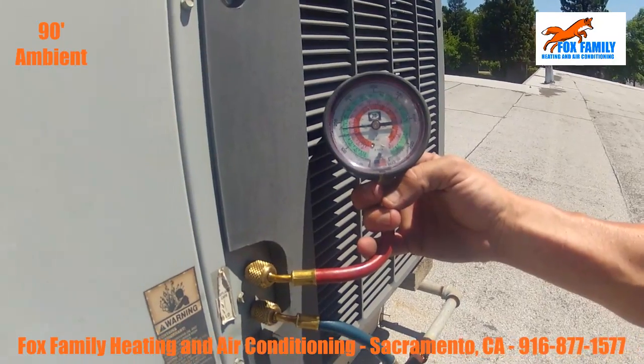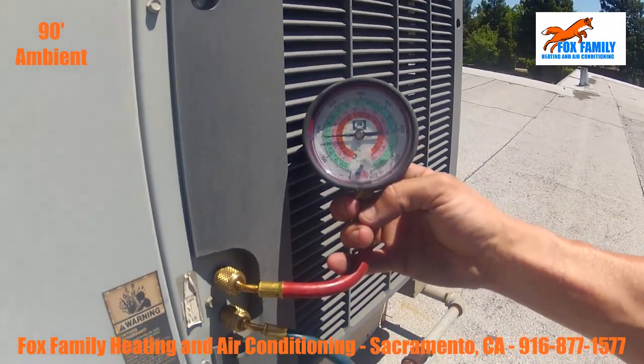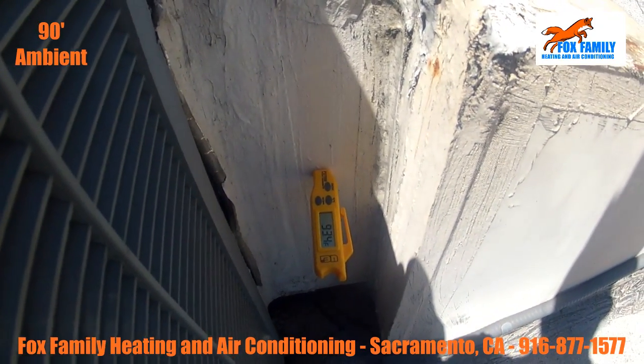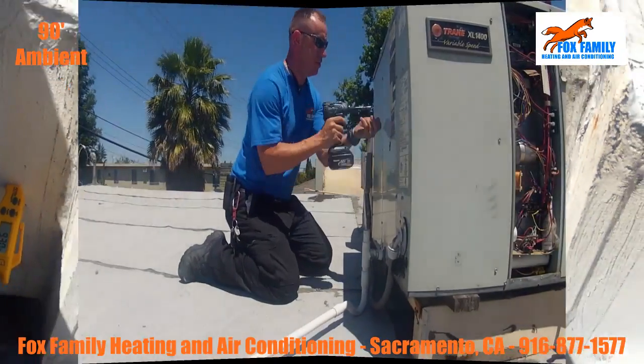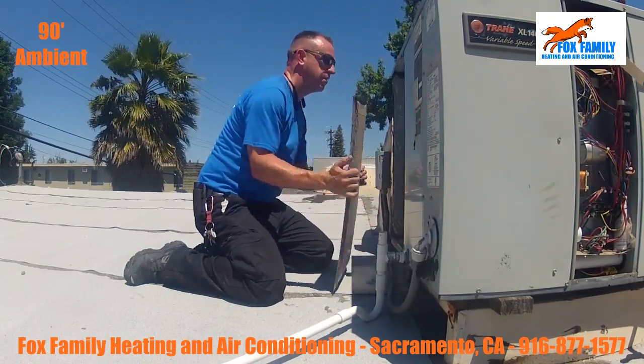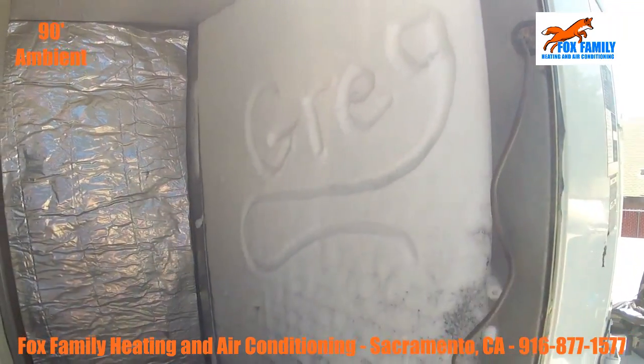And here we're at about 90 degrees saturation. And on a 90-degree day, that's not very good. Still at 93, that's not very good. Hey, we're all frosted up right now. No airflow. No airflow coming through. I think we're low on charge.